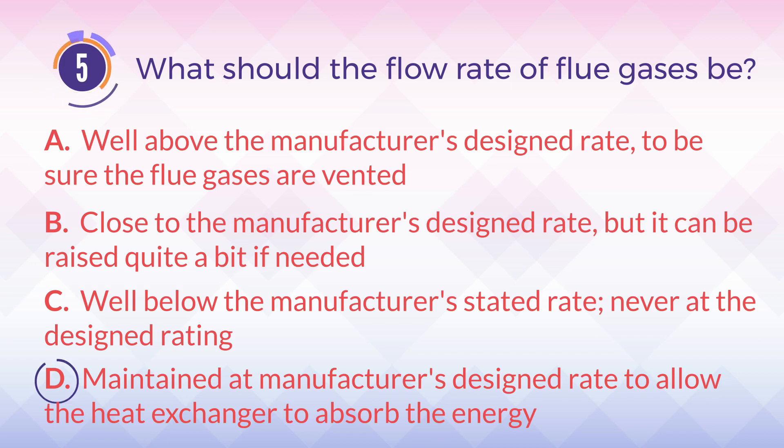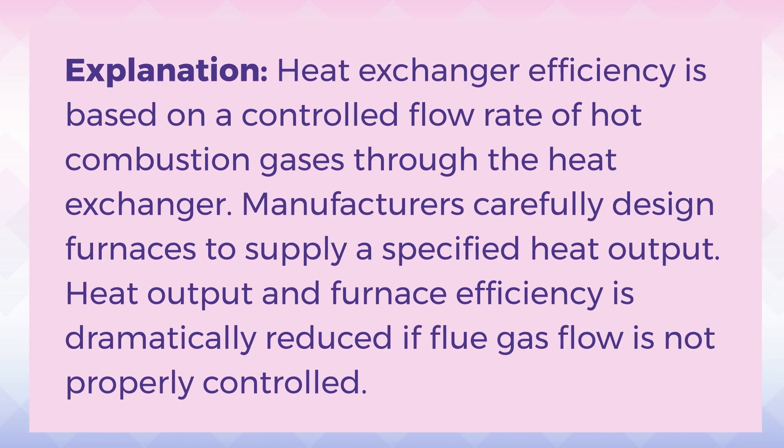The answer is D: maintained at the manufacturer's designed rate to allow the heat exchanger to absorb the energy. Heat exchanger efficiency is based on a controlled flow rate of hot combustion gases through the heat exchanger. Manufacturers carefully design furnaces to supply a specified heat output, and furnace efficiency is dramatically reduced if flue gas flow is not properly controlled.